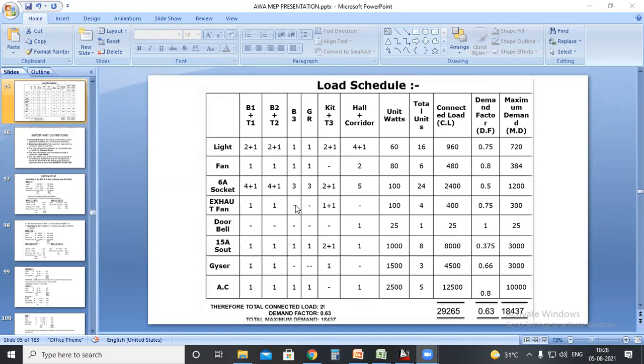As per the standard which we are following right now, you must follow your particular native or your particular state standard. As I told, here in Kerala, especially, they follow the Indian standard, and we can take two general sockets. If I know I am using this particular socket for a microwave, I should know the standard load for a microwave. If the load exceeds a particular limit like 1500 watts, I must take only 1 point.